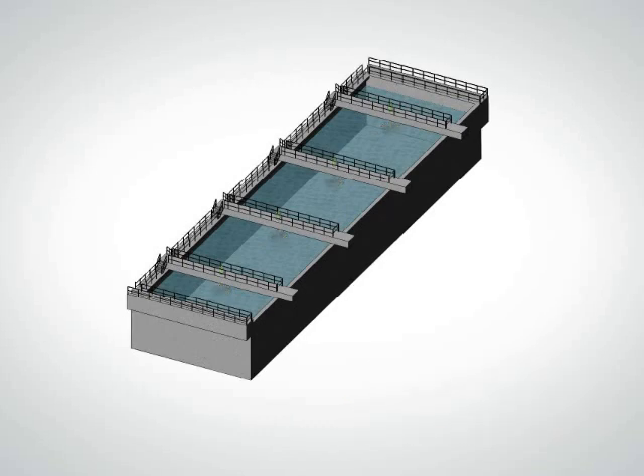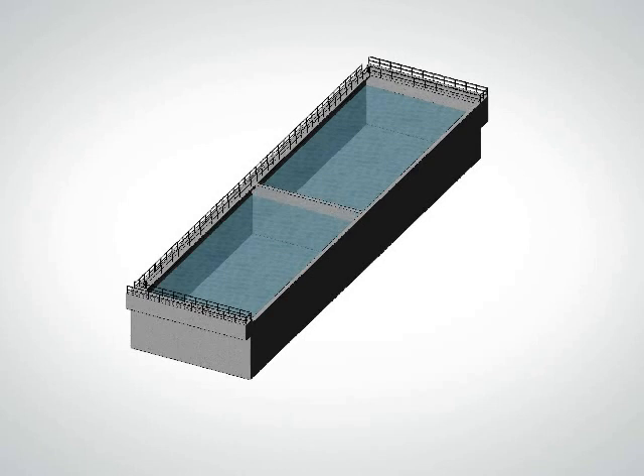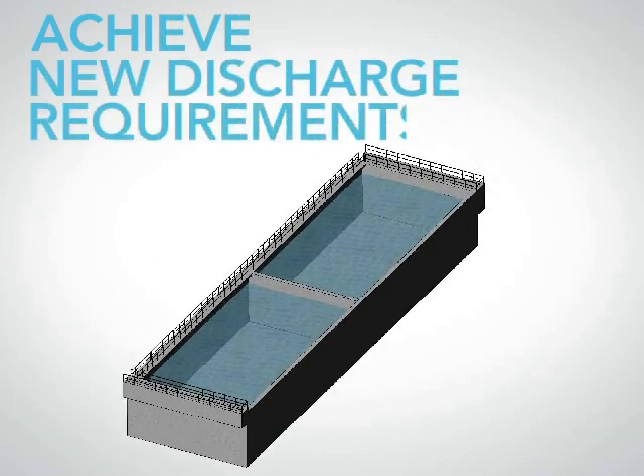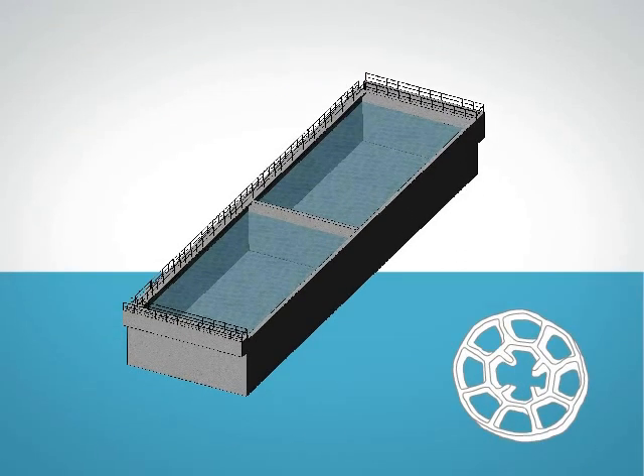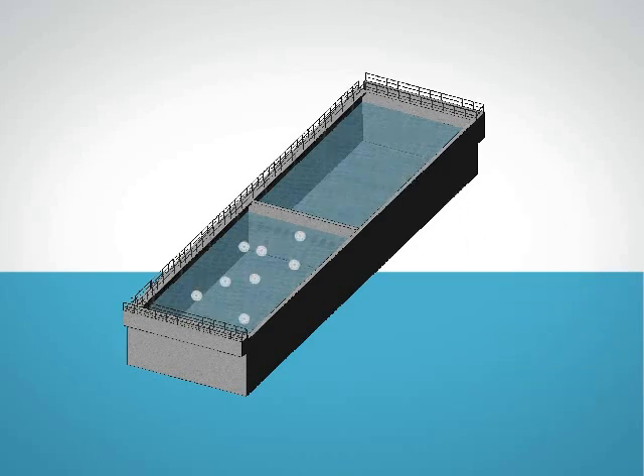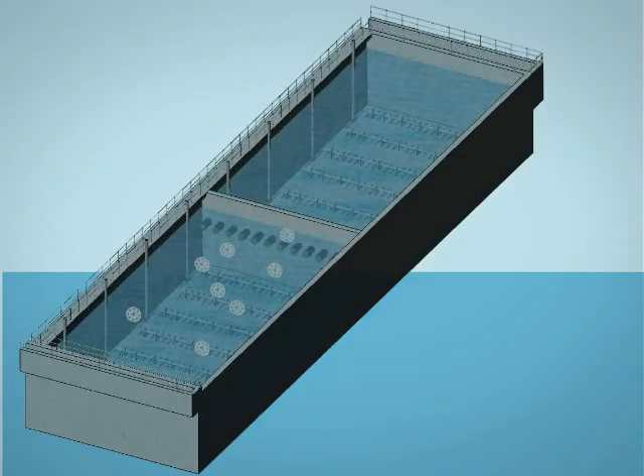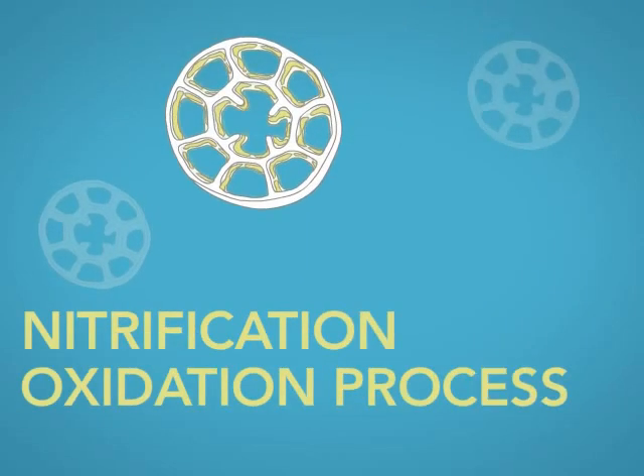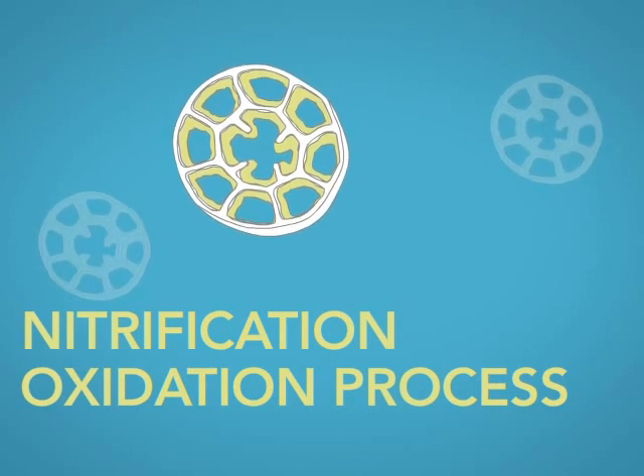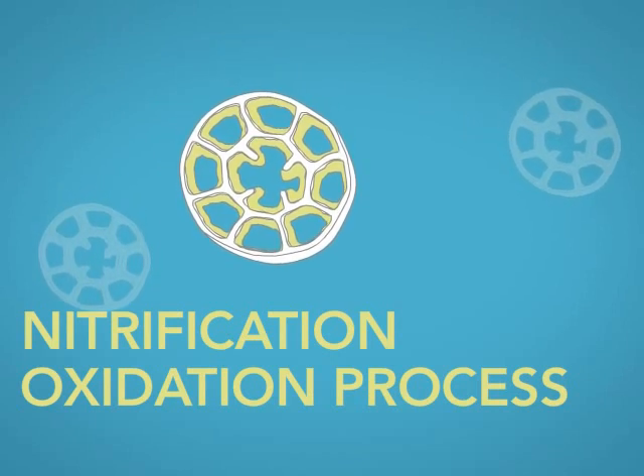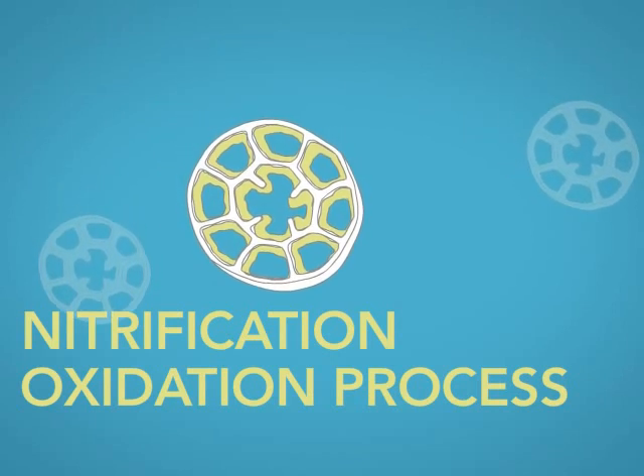In a typical retrofit, new separation walls are added to the existing basins to create process-specific bioreactors to achieve new discharge requirements. In the nitrification reactor, biocarriers, a stainless steel coarse or medium bubble aeration grid, and retention sieves are installed. After a brief media wetting period, biofilm develops on the biocarriers to support the autotrophic bacteria population required for the nitrification oxidation process.